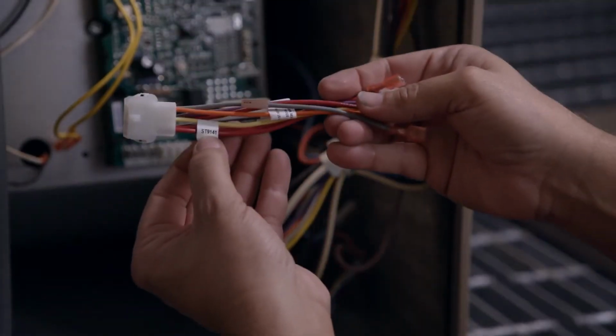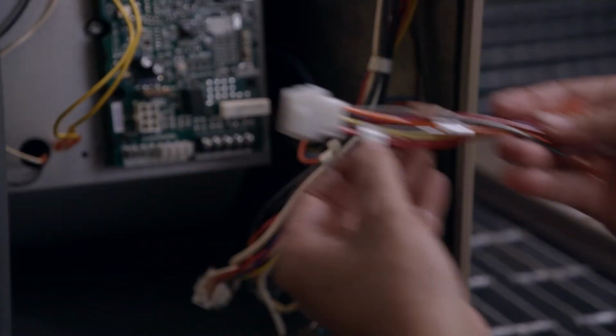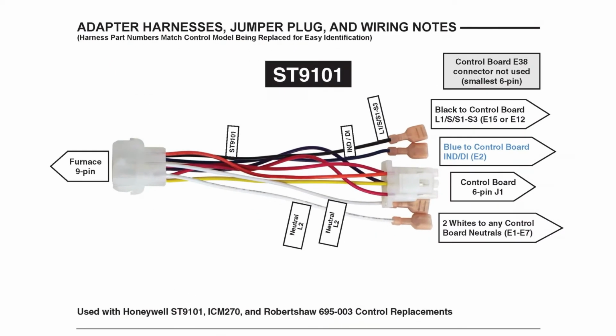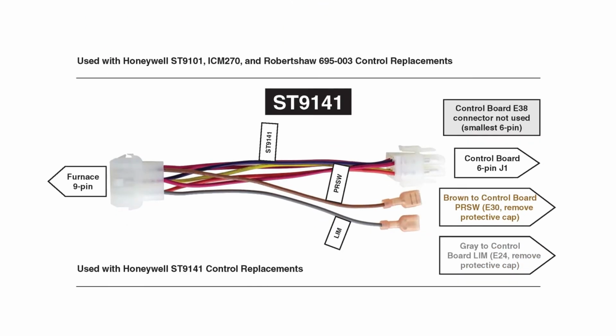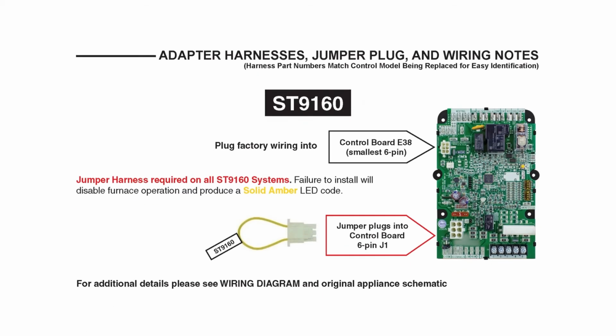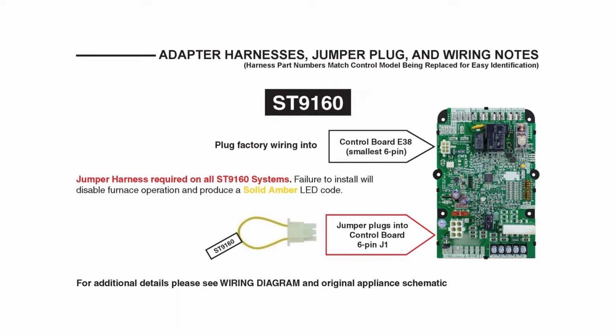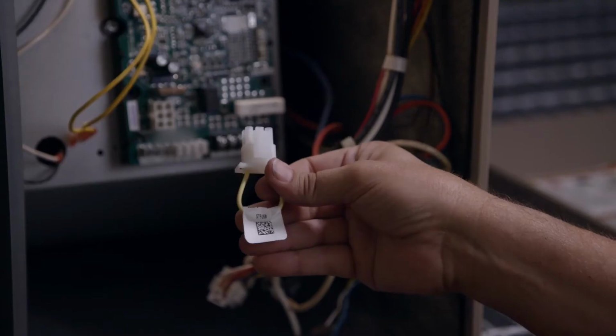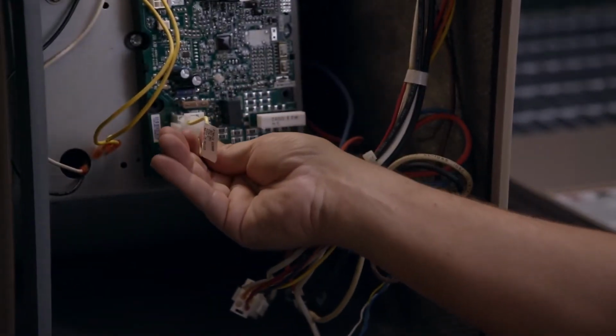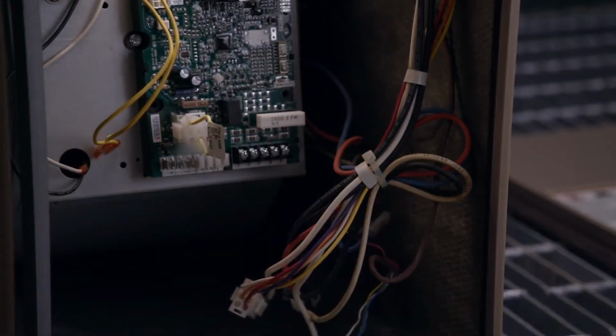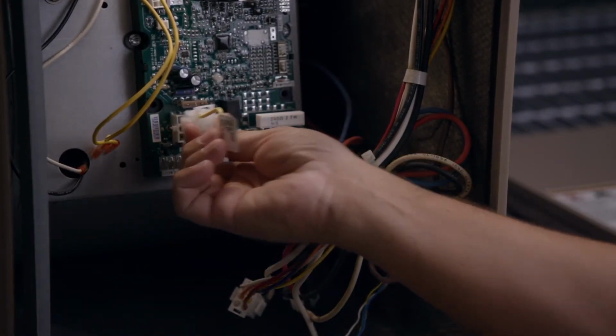Harness part numbers match the control model being replaced for easy identification. If replacing an ST9101 or an ST9141, a harness is required and detailed instructions are included for proper installation. A jumper harness is required on ST9160 systems. Failure to install will disable furnace operation and produce a solid amber LED code. The jumper plugs into the control board 6-pin connector plug. In this case, the part is not needed and can be discarded.